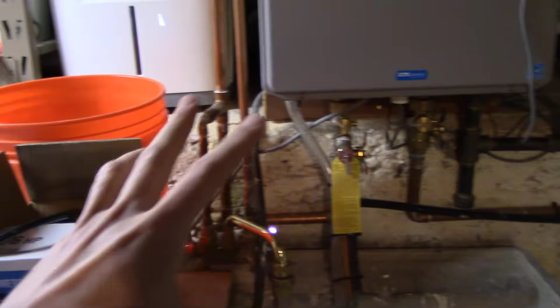Let's cover what products you're going to need in order to do this annual maintenance. The biggest ticket item is the pump, because to do the maintenance, we're going to basically create a closed circuit loop where we're going to pump vinegar through the system in order to descale the heat exchanger. So we need a pump.